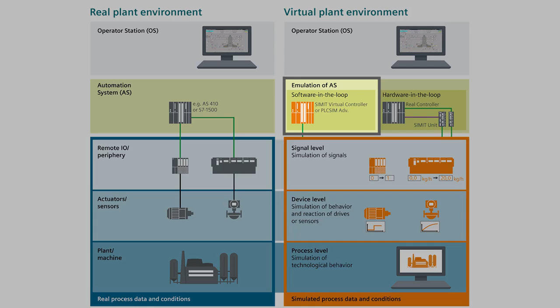As you already know, SIMIT consists of three different levels: the signal, device, and process level. Virtual commissioning affects all these levels. At the signal level, signal and loop checks can be conducted easily by forcing signal values. Decoupling can be done with the real hardware of the automation systems, also called hardware in the loop, and with the integrated virtual controller or the SIMATIC S7 PLC SIM Advanced, and therefore without any real hardware besides the PC station. This is also called software in the loop.